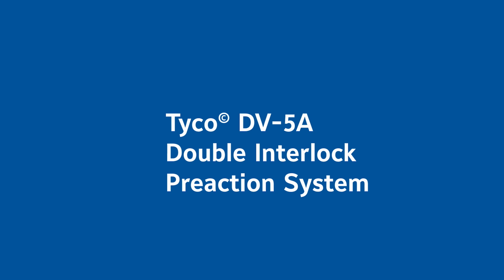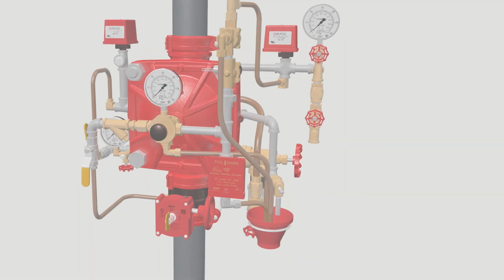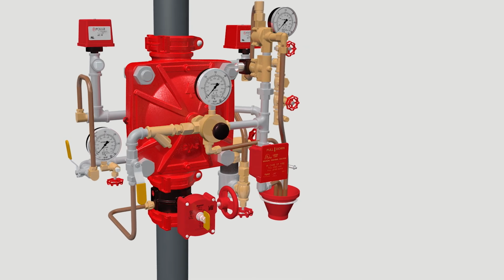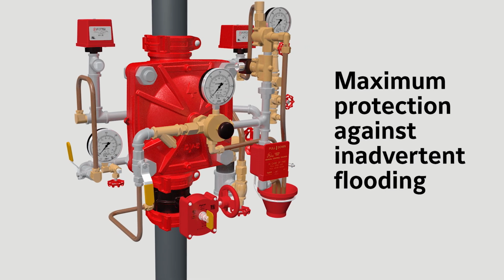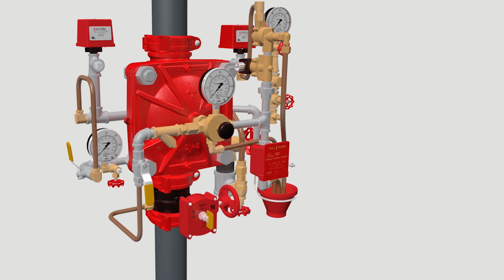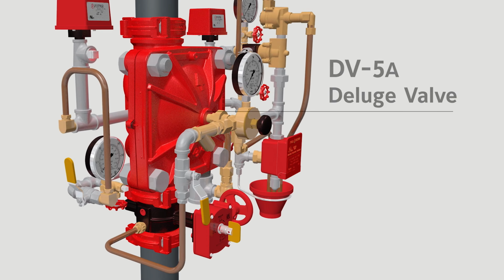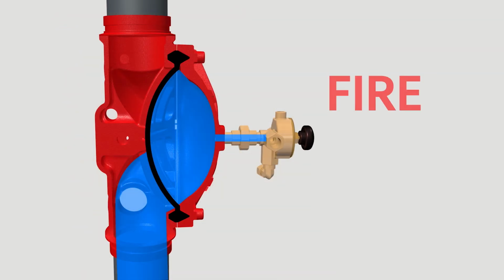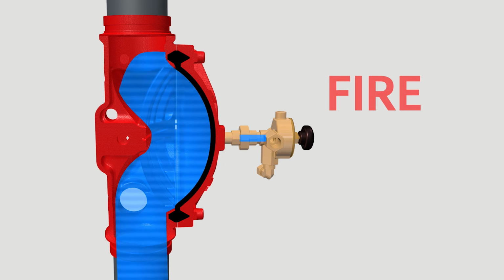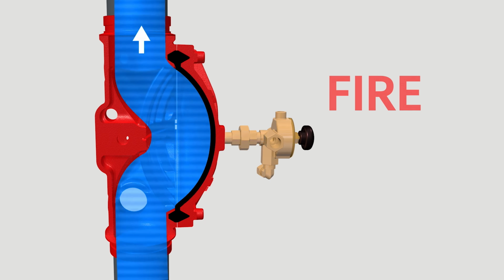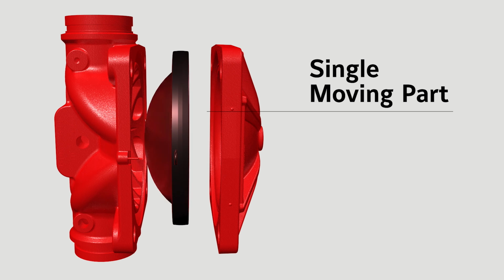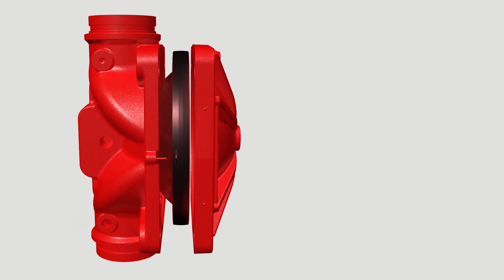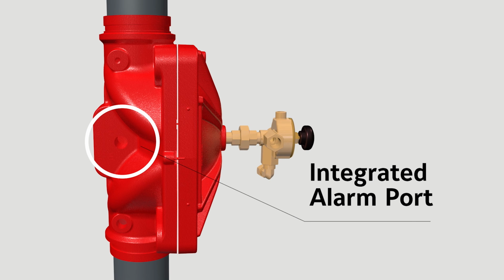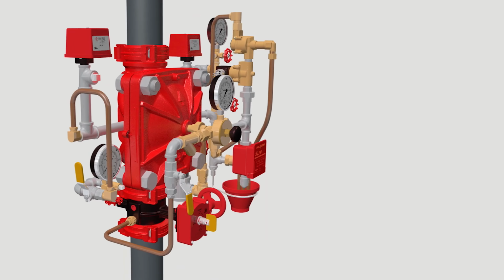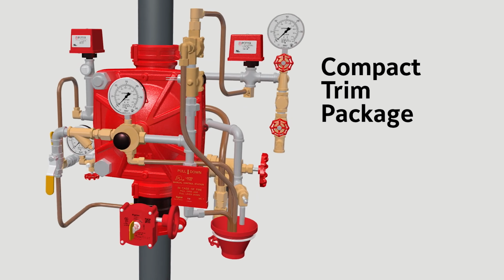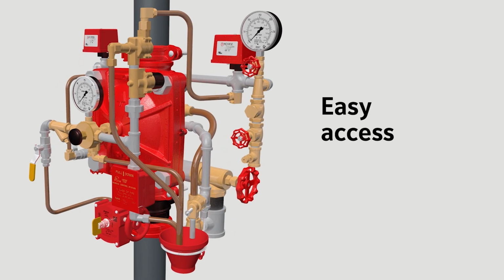The DV5A double interlock pre-action system is designed for use in applications such as refrigerated areas requiring the maximum degree of protection against inadvertent flooding from the sprinkler system piping. The heart of the system is the DV5A deluge valve. When a fire is detected, the system opens the deluge valve, allowing water to travel to the automatic sprinklers to suppress the fire. The DV5A's single moving part simplifies maintenance and provides dependable performance. The integrated alarm port provides a compact design. No additional check valve on top of the valve is needed. The DV5A is part of Tyco's compact trim package, specifically designed for easy installation, access, and maintenance.